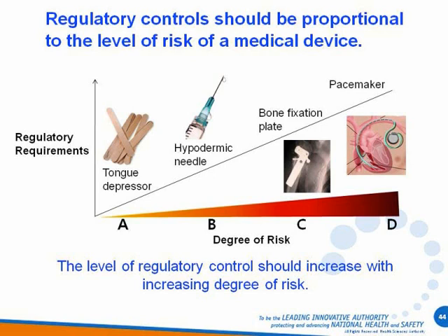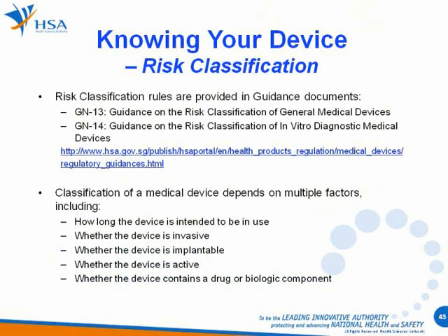The higher the risk presented by a particular medical device, the tighter will be the level of regulatory control to be imposed on that device. The risk classification of a medical device depends on multiple factors, such as the duration of medical device contact with the body, which includes whether the device is implantable, the degree of invasiveness, and whether the device is powered by an external source of energy, or whether the device contains a drug or biologic component.